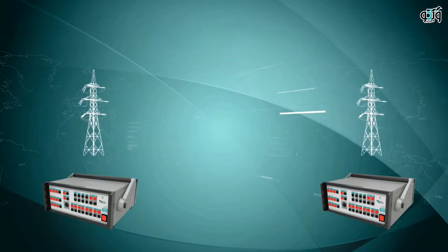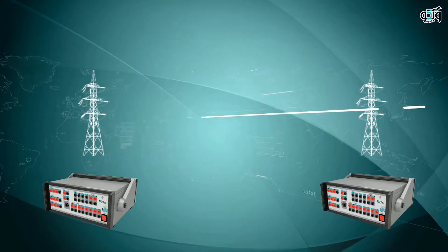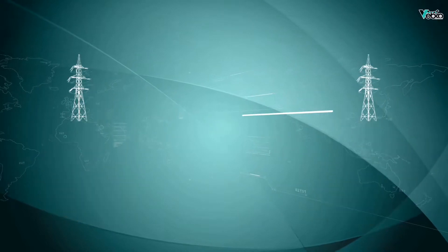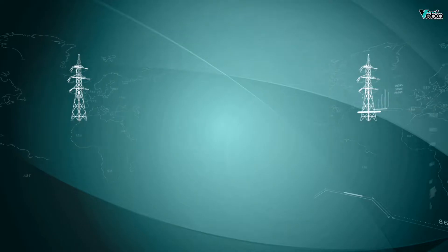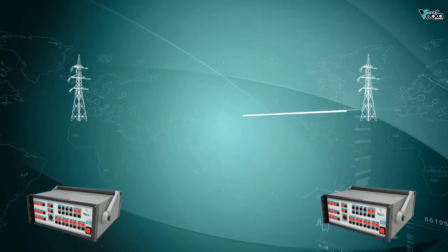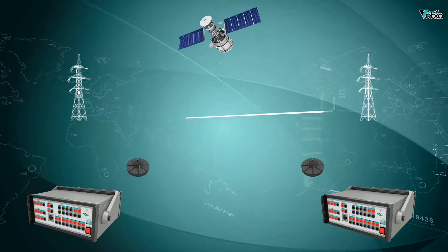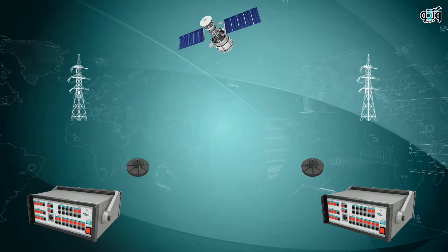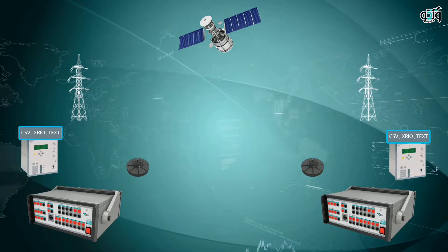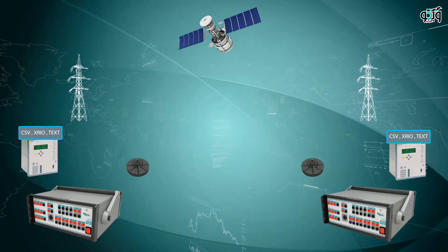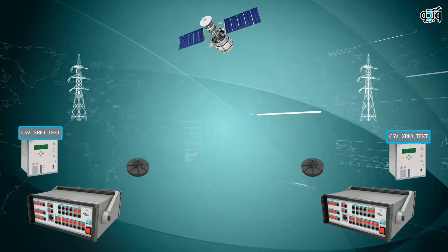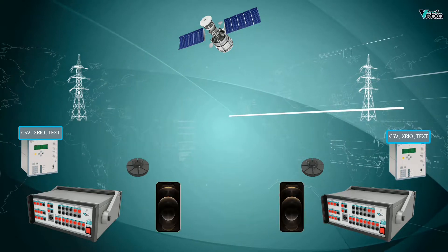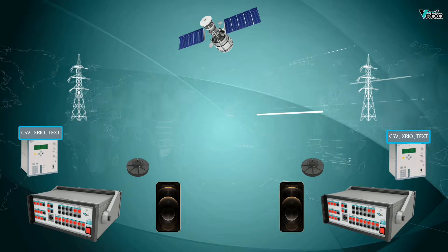In end-to-end tests, two or more test devices are used on each side to simulate the fault. To successfully perform an end-to-end test, the following elements are needed: a test device on each side, a hardware piece to synchronize the two devices like a GPS satellite, a file exported from the relay software in CSV, XRIO, text or other formats, and communication equipment such as a phone or two-way radio to communicate with the other posts.